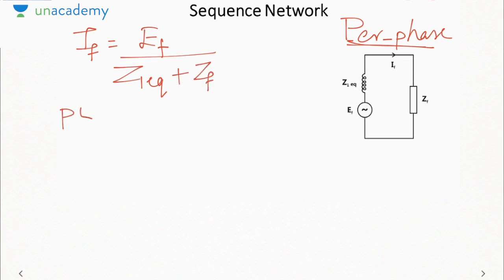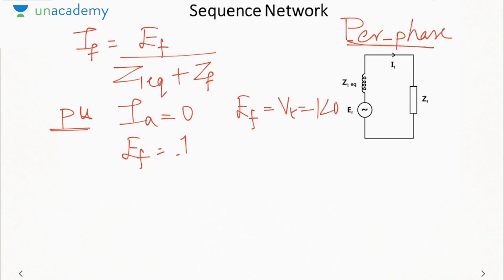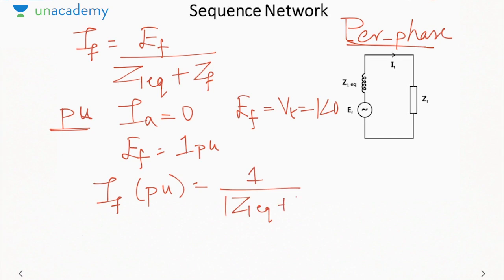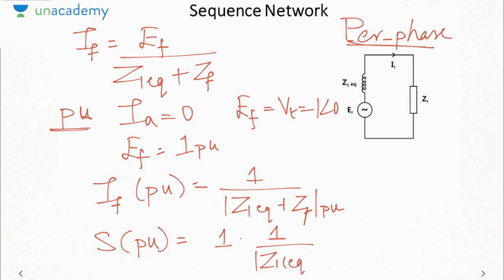in PU, under no load condition, what will happen? IA will be 0, so EF will be equal to VT, which is equal to 1 angle 0. So EF will be 1 PU. So what will be the IF in PU? It will be 1 upon mod Z1 plus ZF in PU. And what will be the power in PU? It will be equal to EMF into current, because in PU power or S is equal to V into I. So it will be the same as that of current.